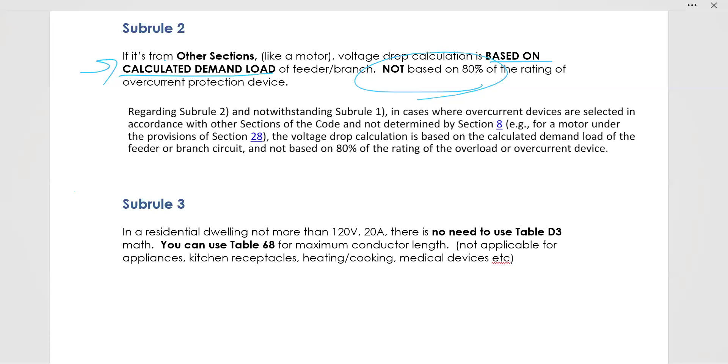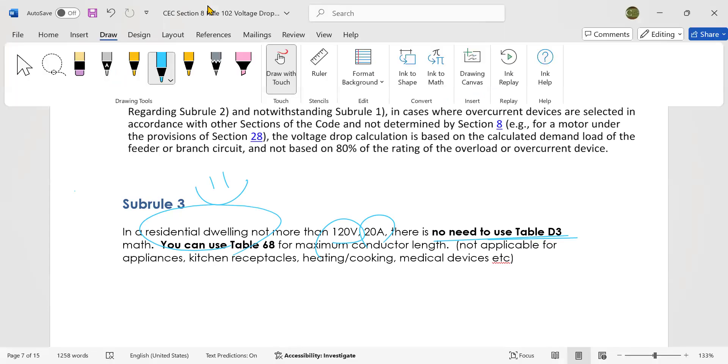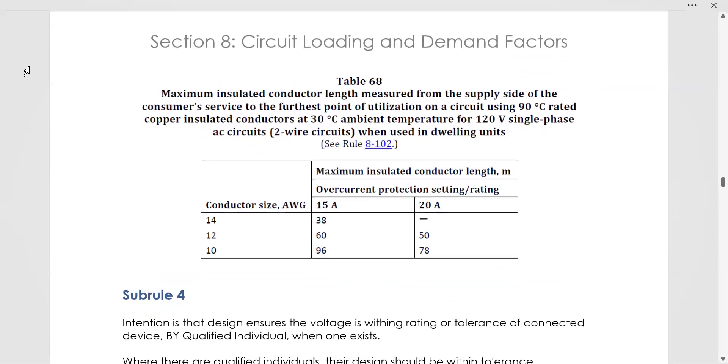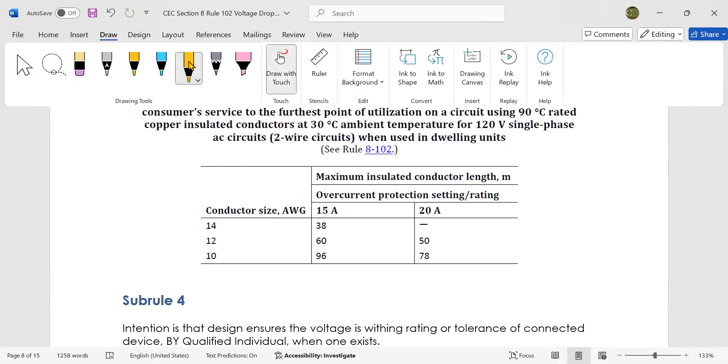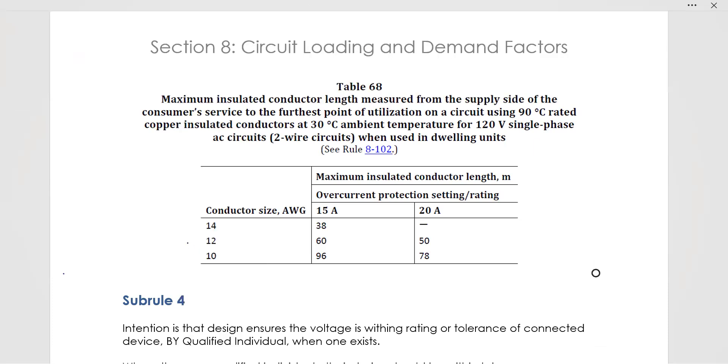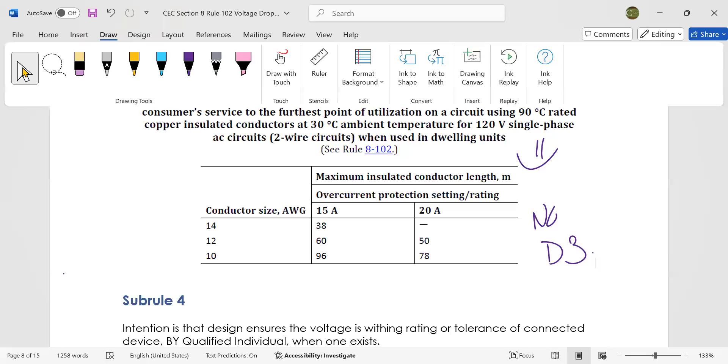Subrule 3 also makes us happy because it says if you're in a residential dwelling, not more than 120 volts and 20 amps, there is no need to use our evil table D3 math. You can just use table 68 instead. So in your codebook, you have to flip a lot to find all of these subsections and rules and everything and find table 68. But here it is here, table 68. If you're in a residential setting of 120 volts, less than 20 amps, then you can use this happy little circuit. You can use, I mean, this happy little table instead. And we can use table 68 and no D3 in residential. That's kind of cool. So we're starting to like this. We're starting to like this section. Okay, here we go.